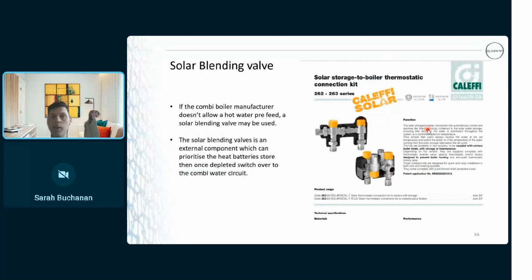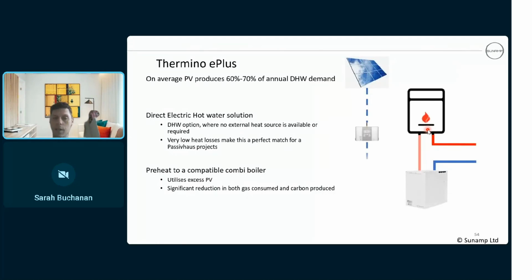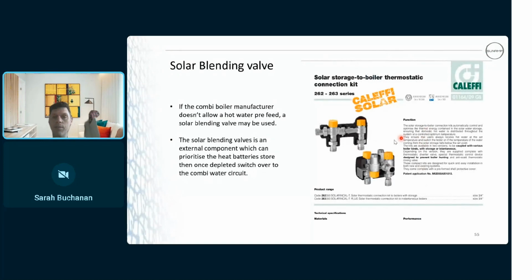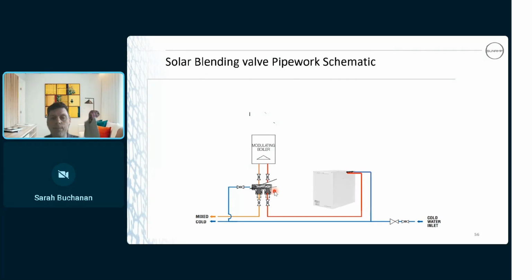But if you do get a boiler that doesn't allow a hot water preheat, you can use a 5-port solar blending valve. All right, so that's your solution to that problem. So if your combi manufacturer doesn't allow a hot water pre-feed, a 5-port solar blending valve can be used. The solar blending valve is an external component which can prioritize the heat battery's store. Then once depleted, it switches over to the combi water circuit. So it's a little bit like that in a nutshell. Once the hot water goes in, you're mixed. Once that's depleted, it just prioritizes the boiler from there.